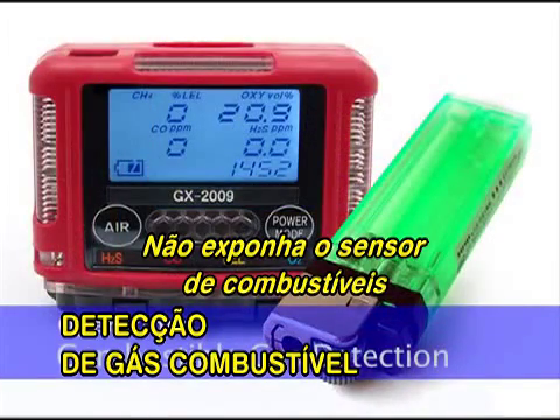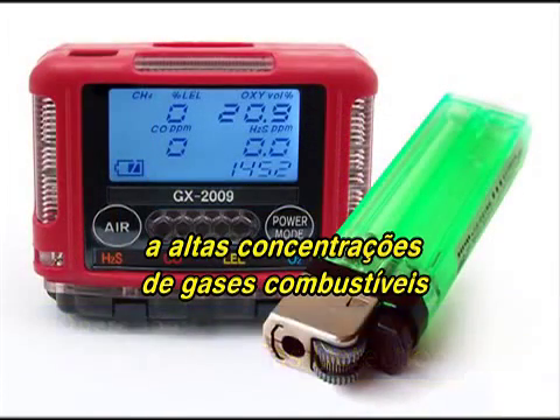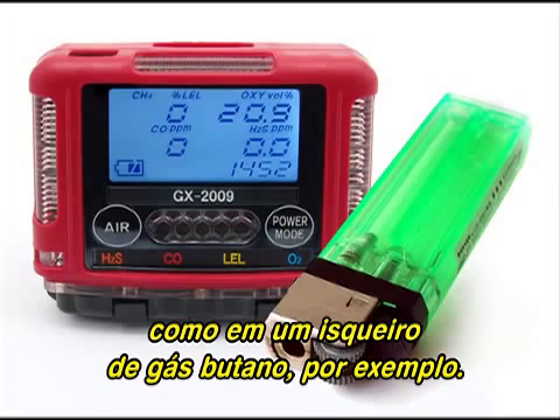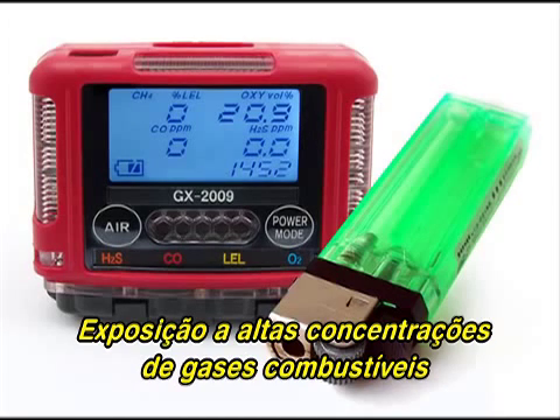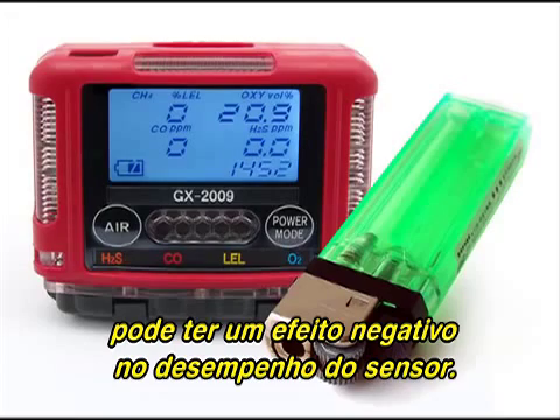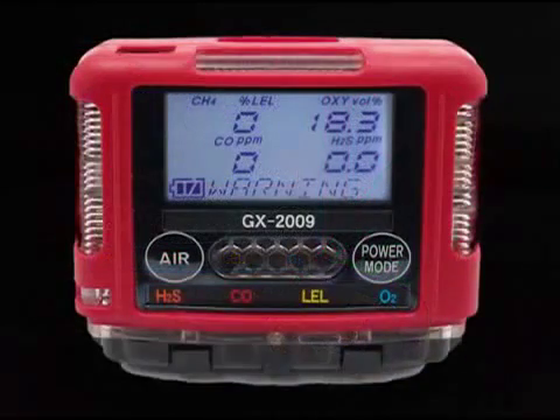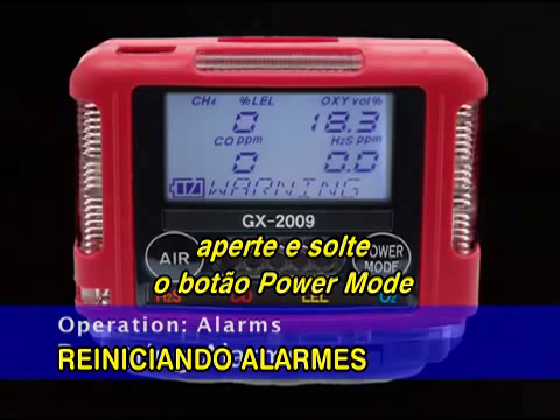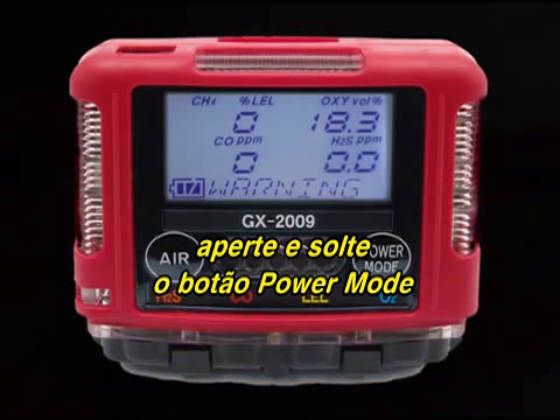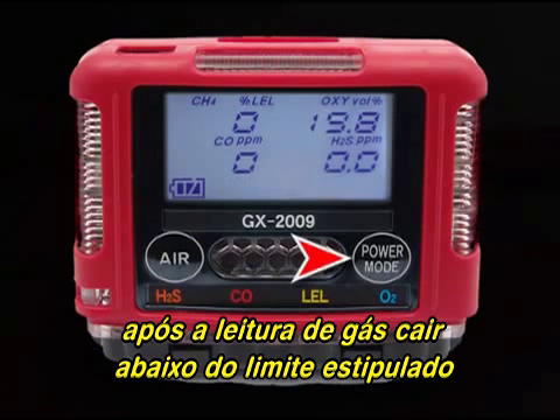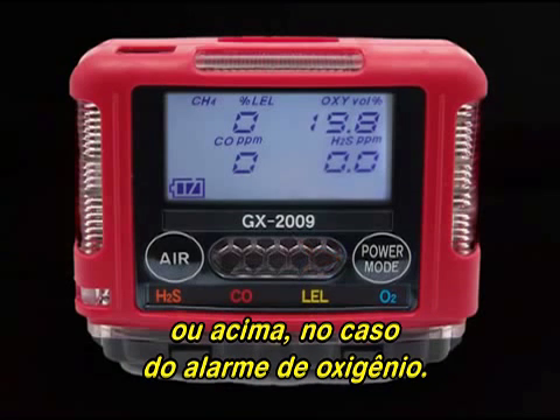Do not expose the combustible sensor to high concentrations of combustible gas, such as that from a butane lighter. Exposure to high concentrations of combustible gas may adversely affect the performance of the sensor. To reset latch and alarms, press and release the power mode button after the gas reading falls below the alarm set point or above for oxygen warning.